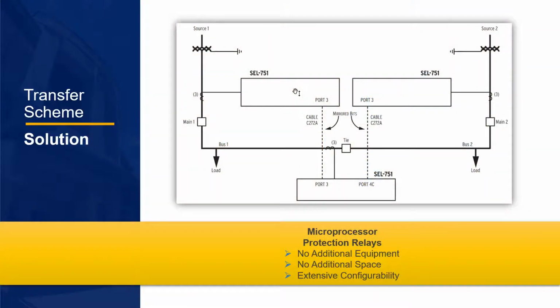One of the main challenges of this project was implementing a new transfer scheme for the main power plant distribution switchgear. In addition to the two substation transformers feeding the main setup, which is typical, the plant also had a backup feed from an external utility connected to one end of the system. To operate the buses safely, you have to have the tie open when both mains are closed, and you must have the tie closed with both mains open when feeding from the backup feeder utility.